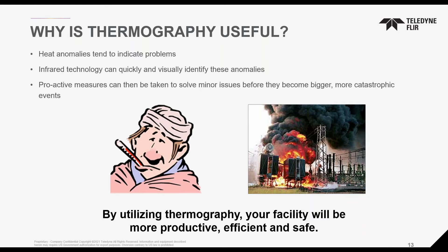Thermography is also non-contact. As the user controlling the camera, you can stand at a distance from the target or asset, as we like to call it in thermography. So you can be separated from energized equipment and don't have to be as close to it, eliminating some of that danger. Also, by taking a non-contact reading, you're not changing that piece of equipment in any way. You don't have to touch it or manipulate the asset, so you're getting a true reading of how it's performing and its temperature.